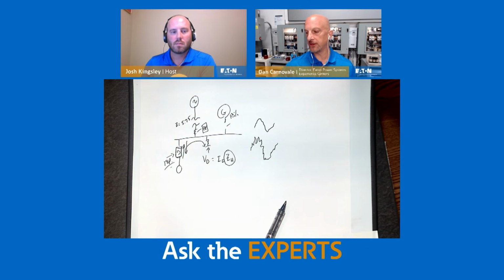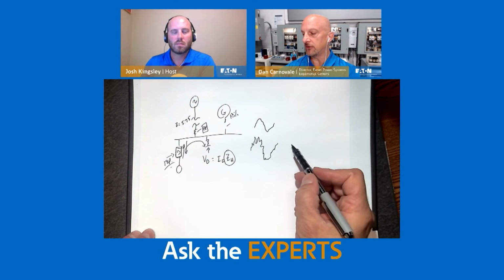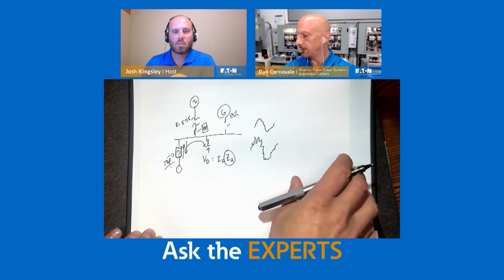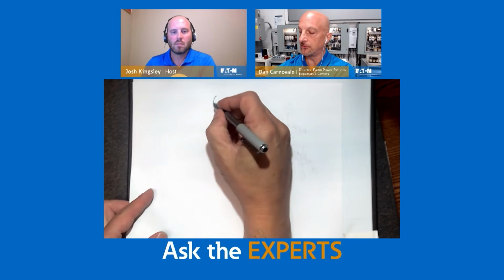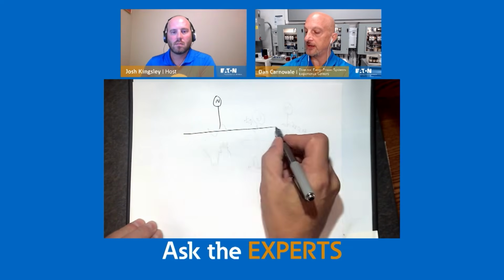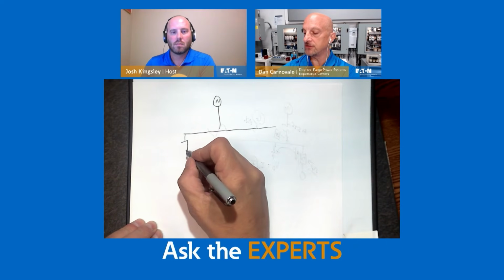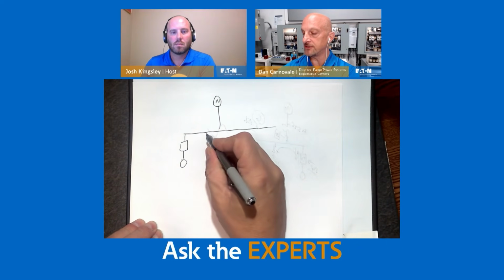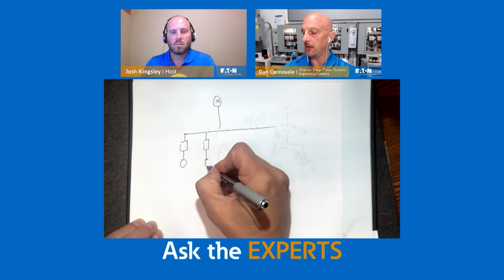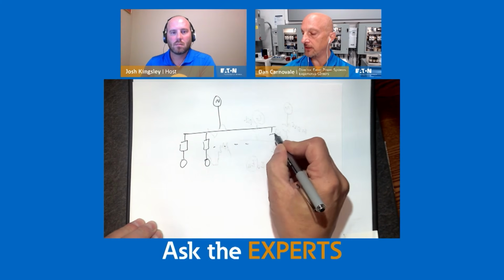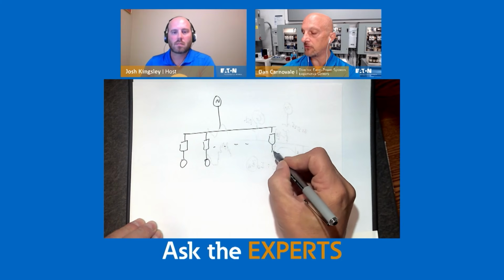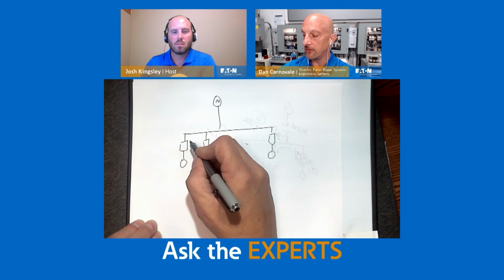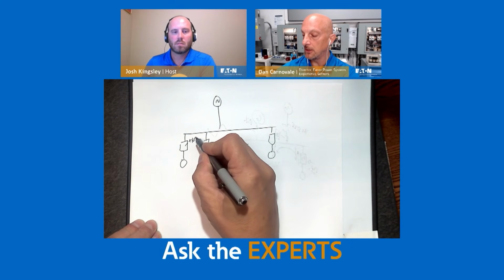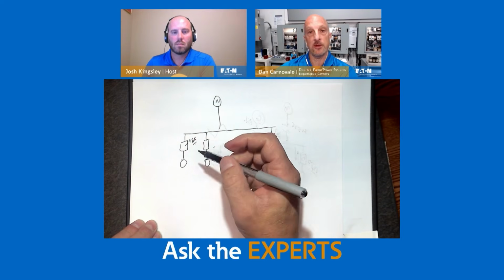And let me just add one more thing to that. Let's say this is a water treatment plant. Let's say you had 10 drives across here. Okay, so I'm going to start actually over here. Let's say you have your source and you have 10 drives. Well, one of the things you could do is put a filter on every single drive, okay? And I won't draw them all out, but if you end up with a filter on every drive, so you have a drive plus a harmonic filter, that adds a little bit of cost to every drive, but it might be the right way to do it.